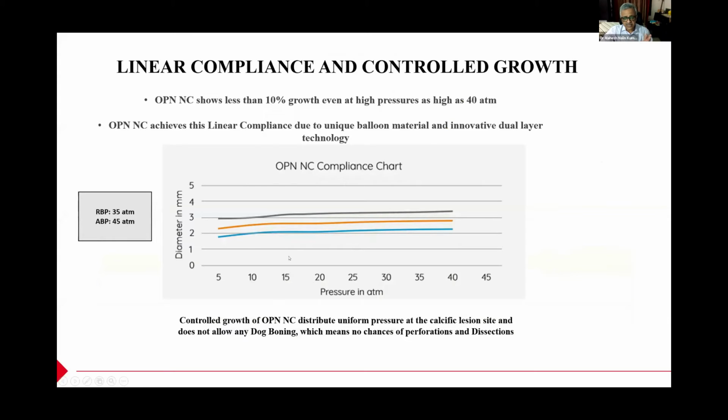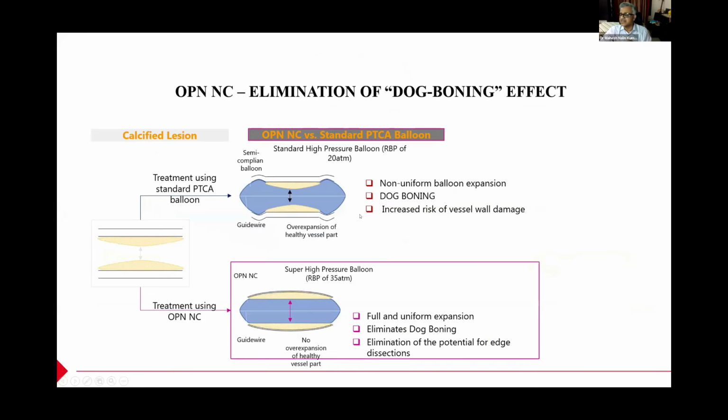And the biggest advantage is that unlike the other balloons, the increase in size is only about 10% when you increase the pressure, even at a rated burst pressure of 35 atmospheres. So it doesn't increase in size.